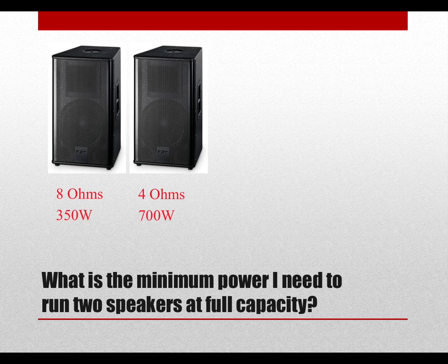If we are running two speakers at the same rating, we would need at least an amp to push 4 ohms at 700 watts. Notice how the ohms were divided and the watts were multiplied. We have two speakers.